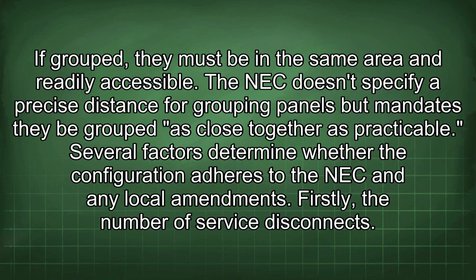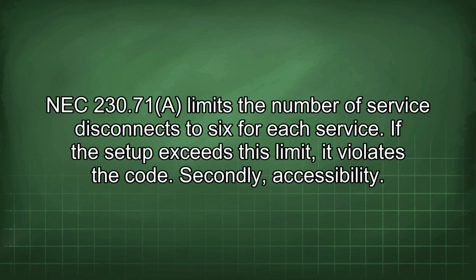Several factors determine whether the configuration adheres to the NEC and any local amendments. Firstly, the number of service disconnects. NEC 230.71 limits the number of service disconnects to 6 for each service. If the setup exceeds this limit, it violates the code.